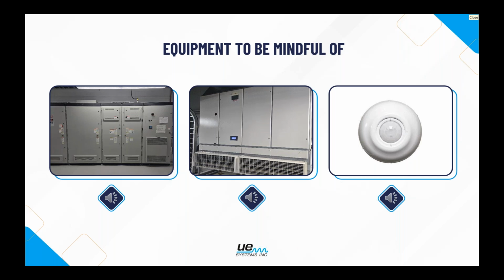So once again, if I was listening to an MCC bucket and I heard that sound coming out of it, I would be immediately concerned, inspect further, and record it. But being aware that this fan was in there, go and inspect it first, get familiar with that sound, almost use it as a baseline for that room itself. Be aware also that in this example, we had just come out of a shutdown and the fan was damaged, and it had actually been inspected. So clearly either something was put back incorrectly or missed during the initial inspection.